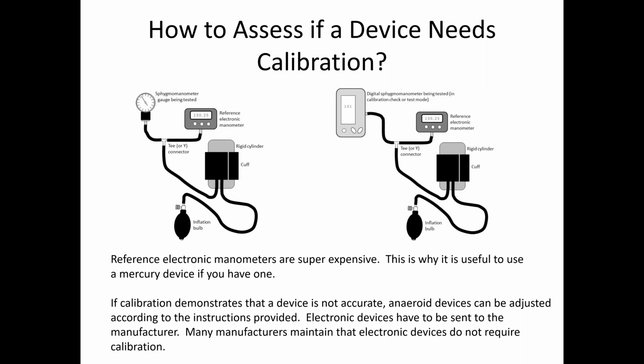The aneroids can be adjusted. Some of them have simple screws, some of them you have to take the faceplate off and just adjust it manually. But there are ways to re-zero aneroids. For electronic devices, this is the real drawback of them. You typically would have to send them back to the manufacturer, which is another reason why I would recommend that in the clinic setting you not purchase really expensive automated office devices. Instead, maybe just go with home units, because if you use a home unit and over time you find it lost its accuracy, you can just replace it. That's probably the easiest thing to do than sending it back.